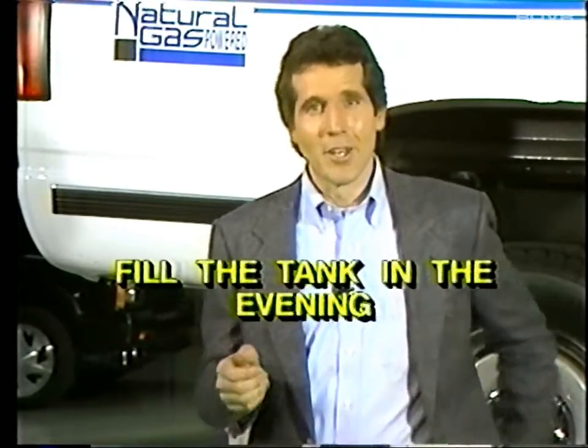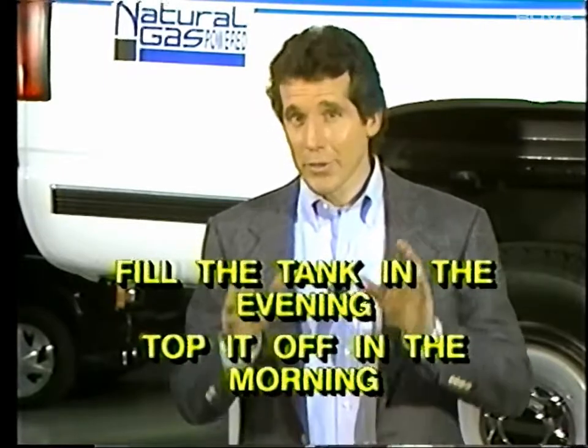The same situation occurs if the tanks are fast-filled to any amount, such as 2,000 or 2,400 psi. Whatever pressure exists at the completion of a fast-fill will be reduced later when the gas cools or stabilizes. To avoid this situation, we recommend that the customer fill the tank in the evening and then top it off in the morning. This is the best way to assure that the gas has stabilized and that the tank is really filled to its fullest capacity.